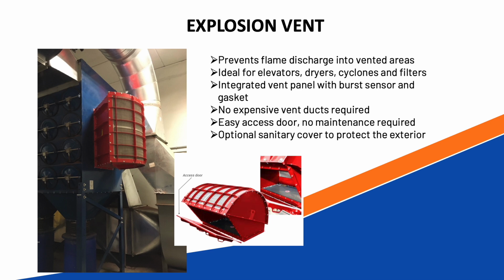If you have an indoor application where you need venting on your collector or your vessel, we can offer a flameless vent that goes on top of the explosion vent. And basically what happens is, in the event of combustion, of deflagration, the vent will open, which will relieve the pressure, and then the fireball will be quenched by the flameless mesh that you see on top of the flameless vent. And basically on the other side of that flameless vent, all you're gonna get is smoke and cloud. We can use these with elevators, dryers, cyclones, filters, whatever type of vessel that you're trying to protect. And we do all the calculations in-house as well.